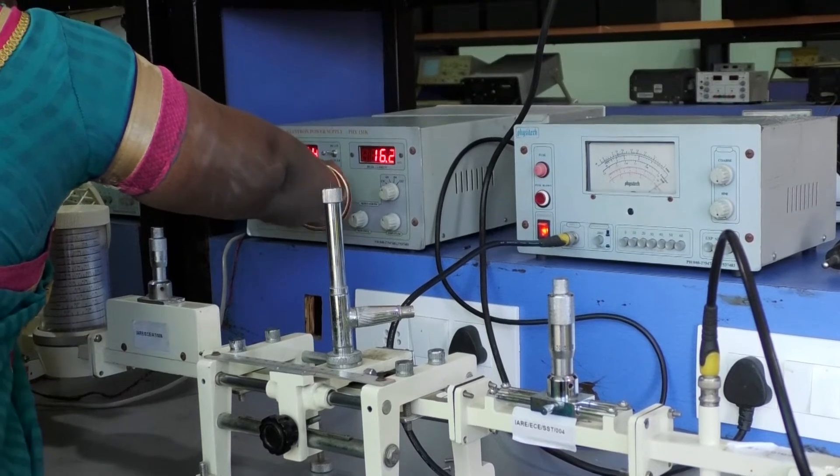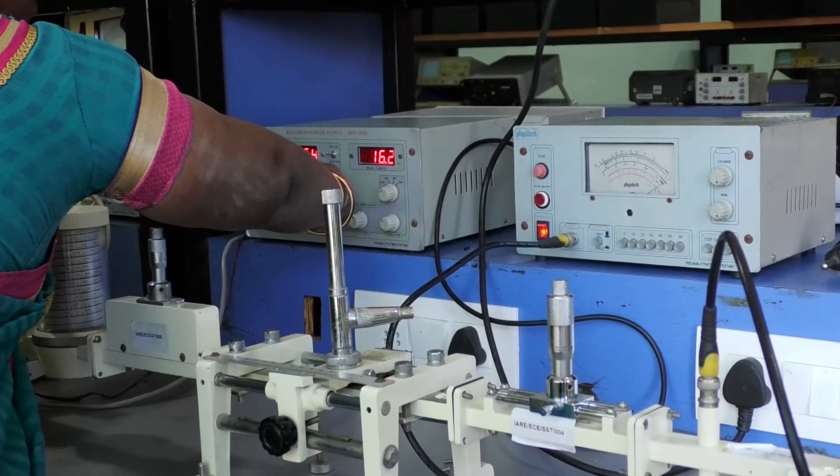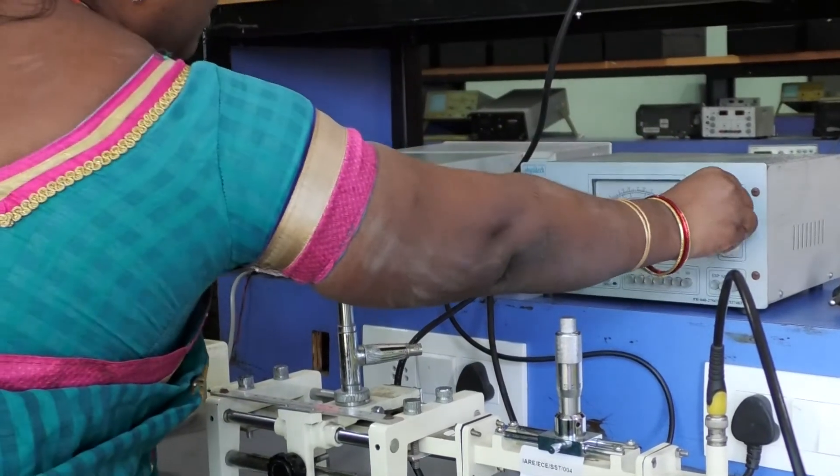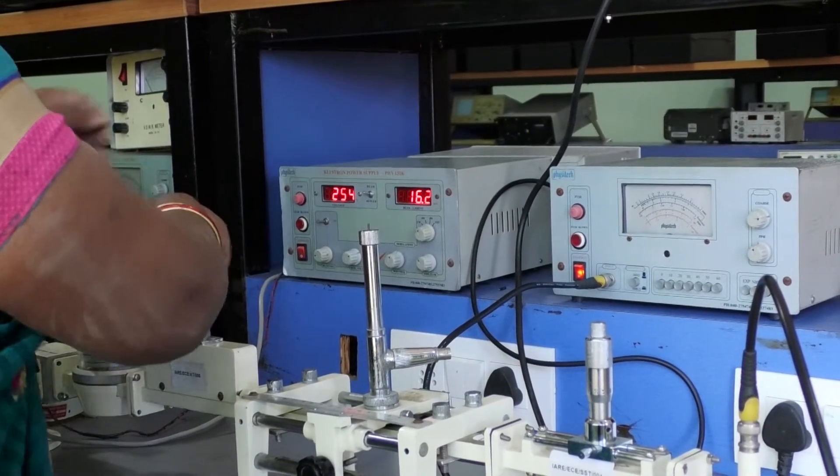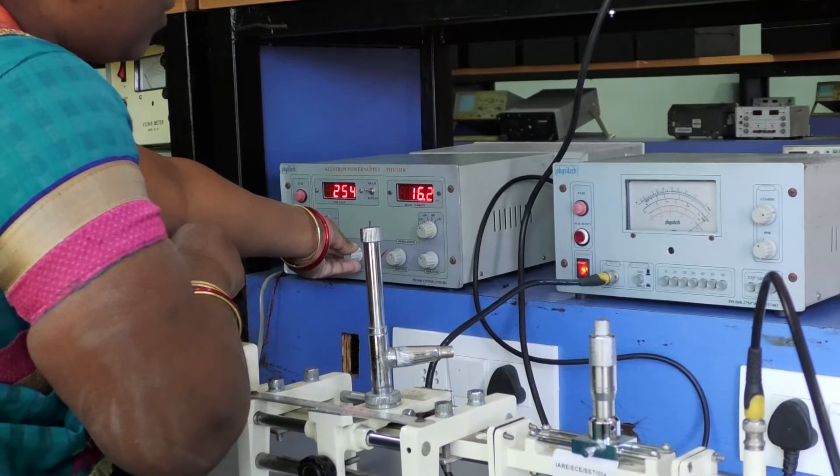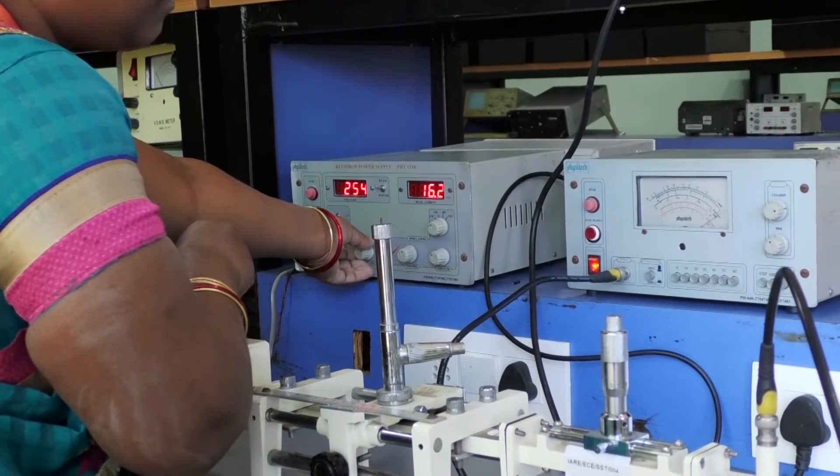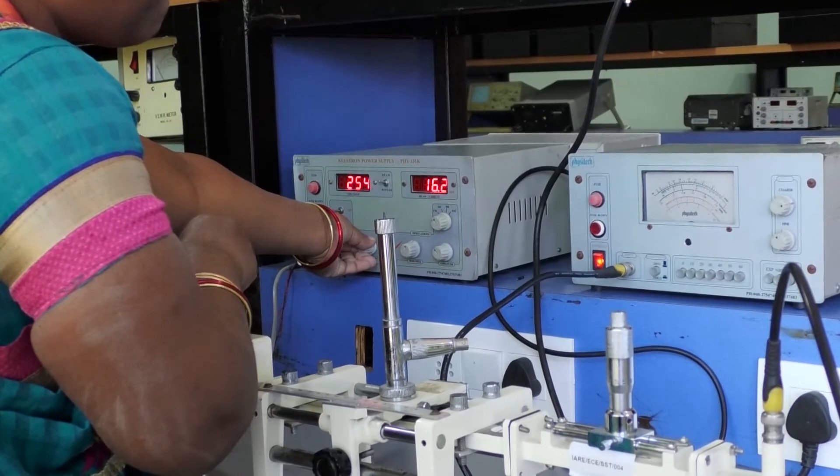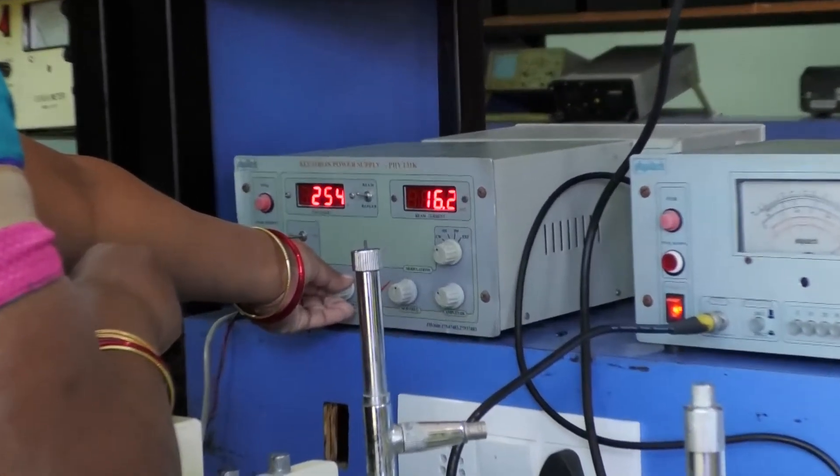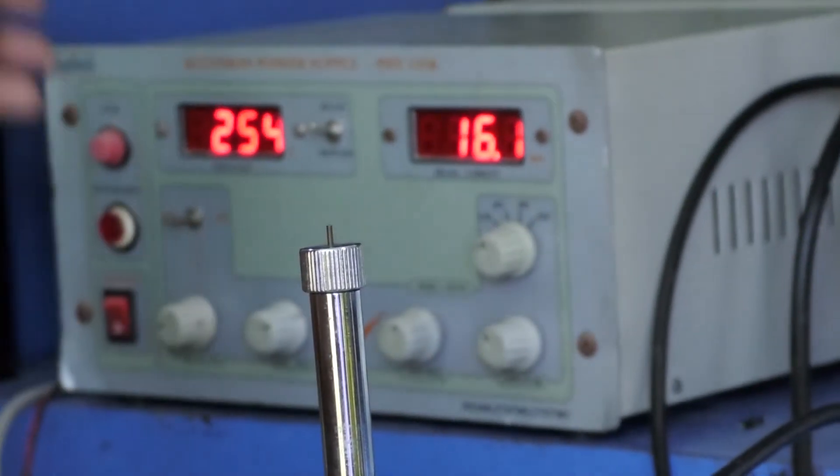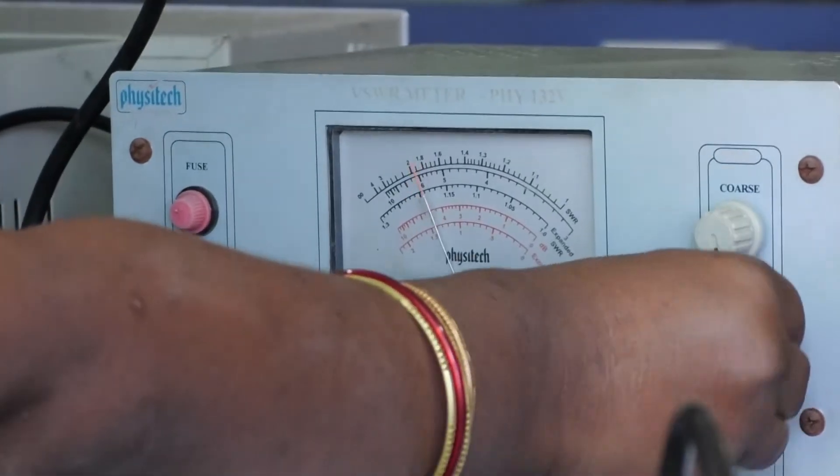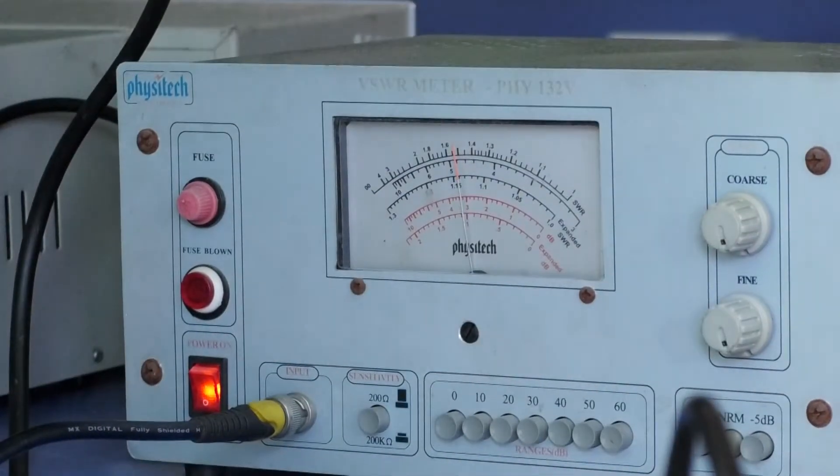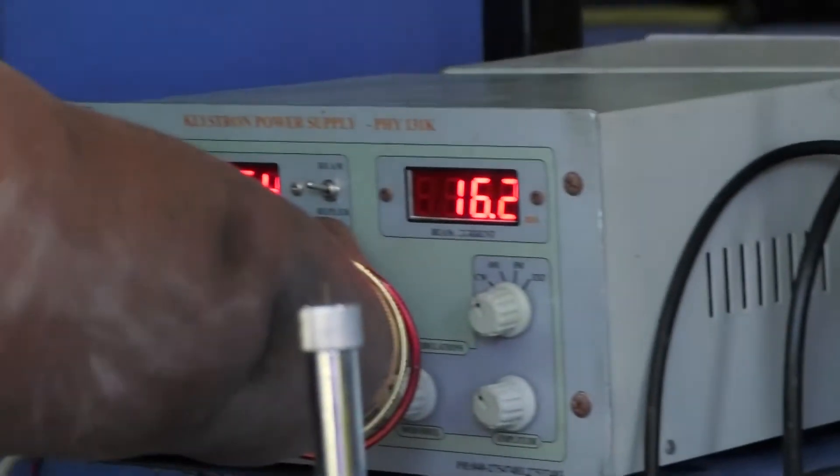After that, again change the repeller voltage to set it to 1. By varying coarse, gain, or variable attenuator position, we have to set VSWR reading as 1.